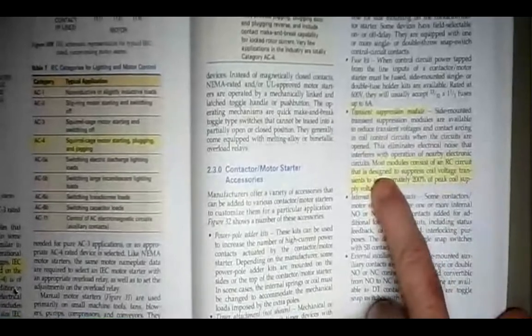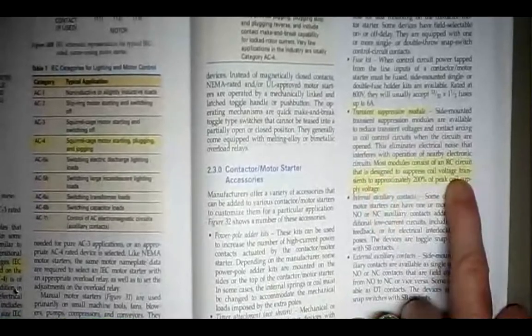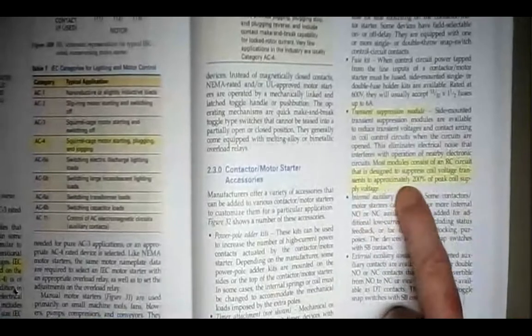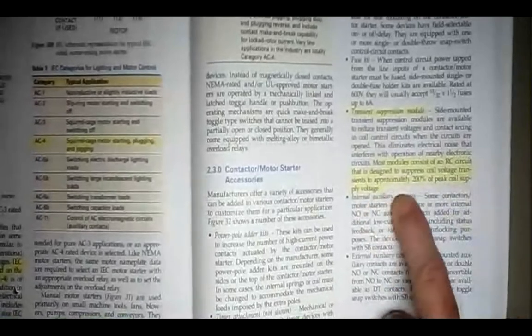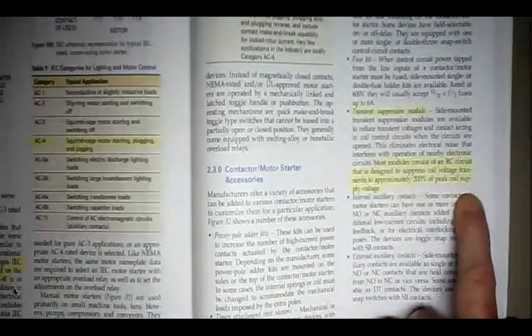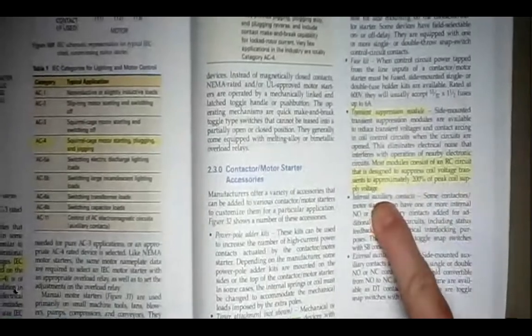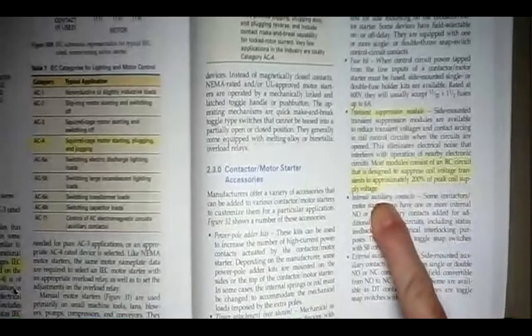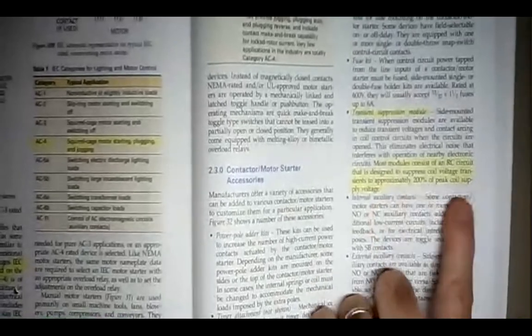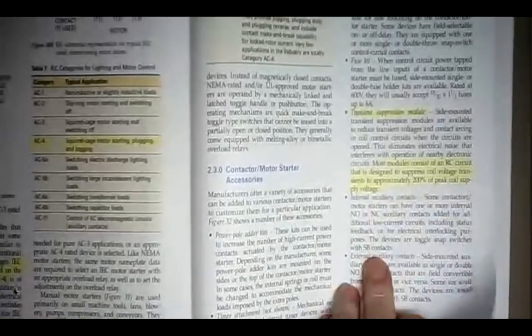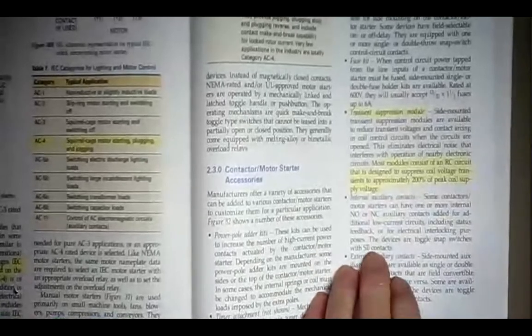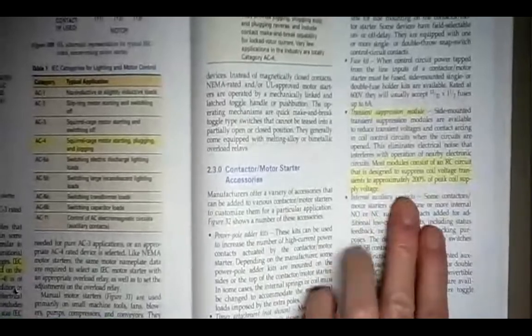This is my highlight. It says most modules consist of an RC circuit that is designed to suppress coil voltage transients to approximately 200% of peak coil supply voltage. So those transient voltages will be suppressed to 200% of peak coil supply voltage. So if the coil supply voltage is 120, it will keep those transients below 240. Okay, that's it for this section. Yes, any questions?